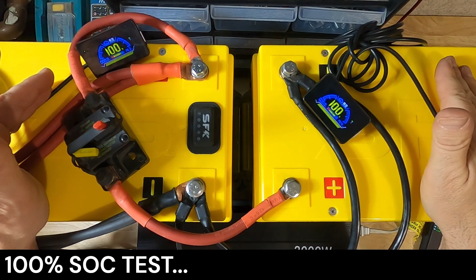Okay, so for our test setup, we have 2 identical batteries and they are connected in parallel. You can see the batteries are exactly charged to 100% and they are connected via this breaker, which is currently in the off position. This is a 100 amp breaker, and the battery on the left we're going to discharge in increments of 25%: 100%, 75, 50, 25 to 0. This battery is connected to the inverter only, so when the breaker is broken, we'll only be drawing power from this battery.